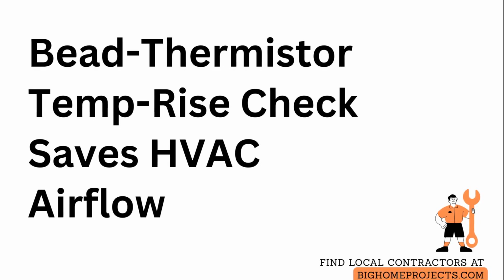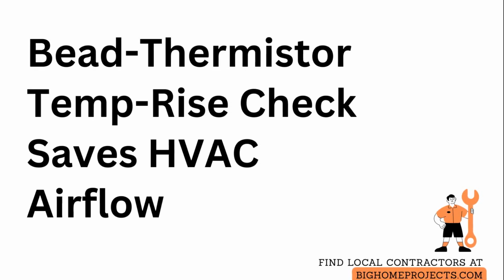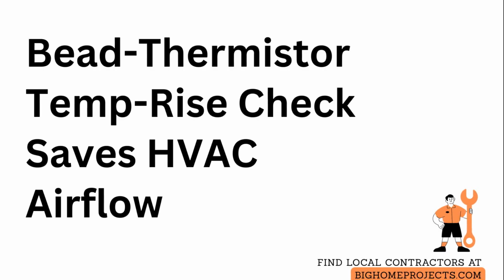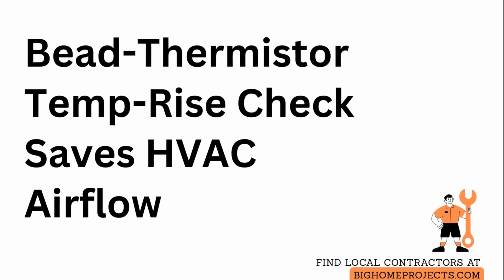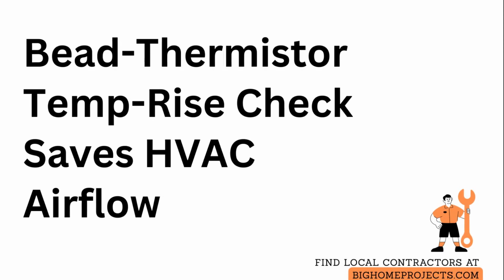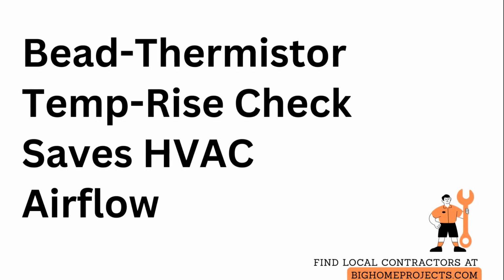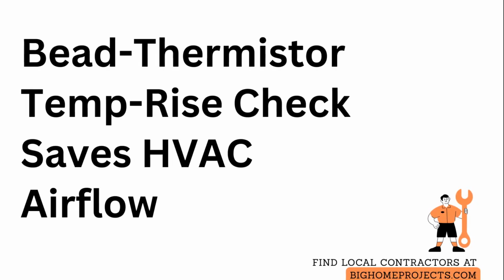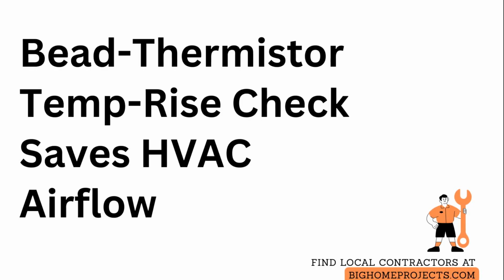HVAC temperature rise testing uses a simple formula. CFM equals the heater wattage divided by the product of the specific heat of air, the air density factor, and the measured temperature rise, so precise temperature sensing is critical for accurate airflow measurement.